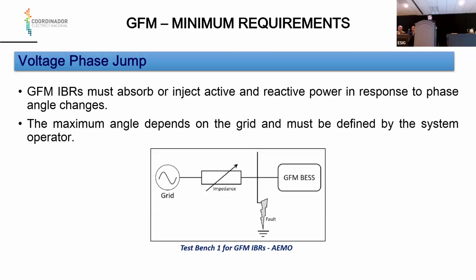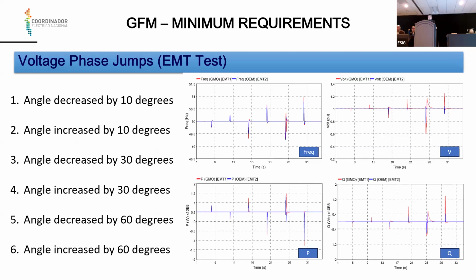The other typical test that defines grid forming that we performed was the voltage phase jump. In this case, we use the AEMO test bench. We look at whether the grid forming unit must absorb or inject active or reactive power in response to the phase angle changes. We performed contingencies of up to 60 degrees, but in our system, maybe that figure must change in our actual system. Here are the results of the EMT simulation with both models, the generic or developed EMT model and the OEM model.